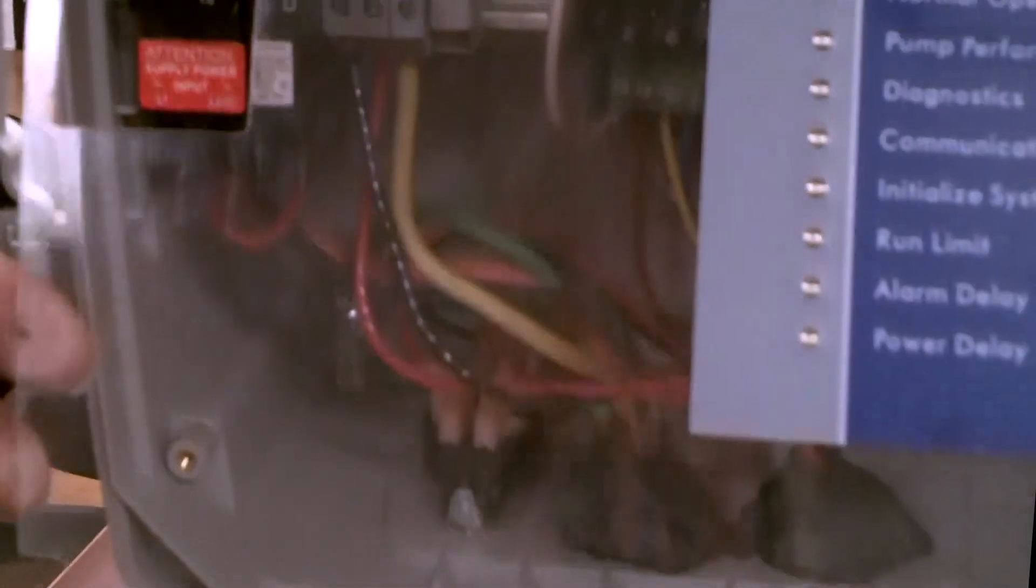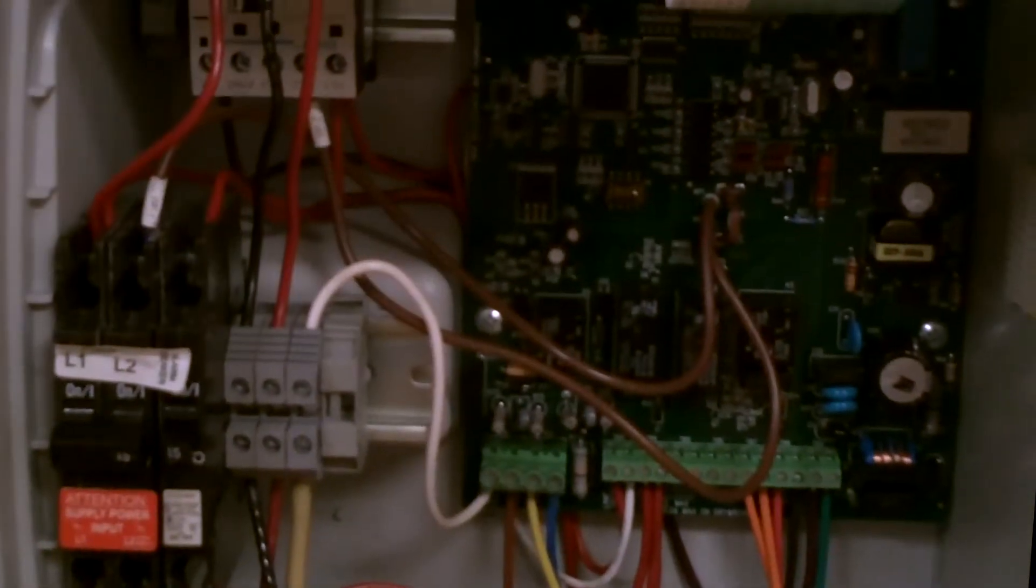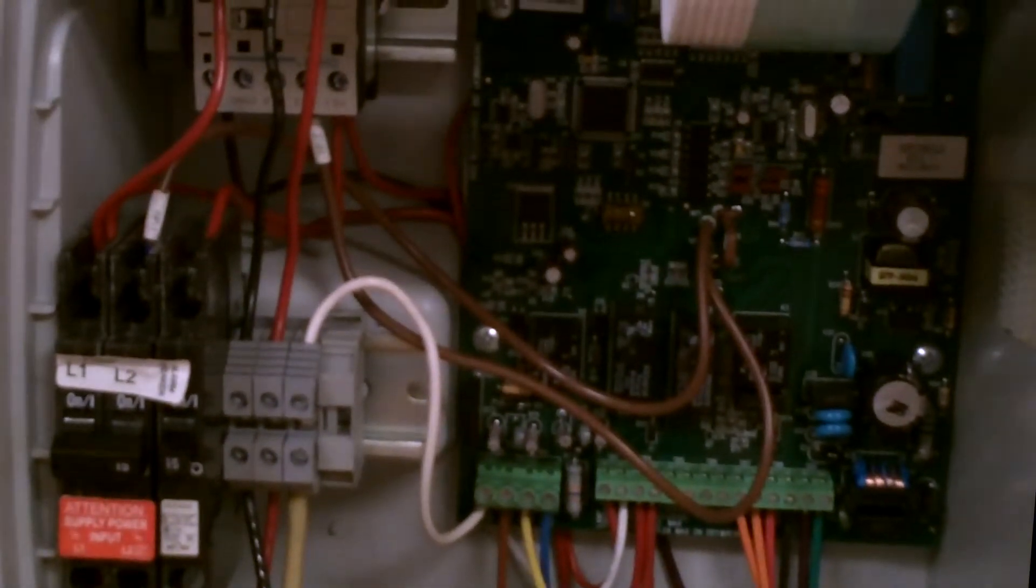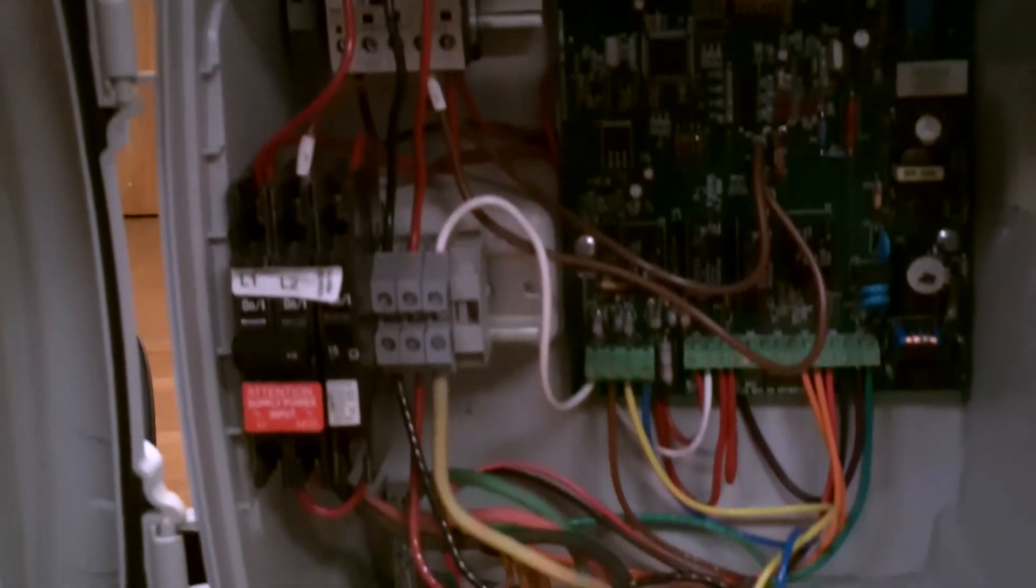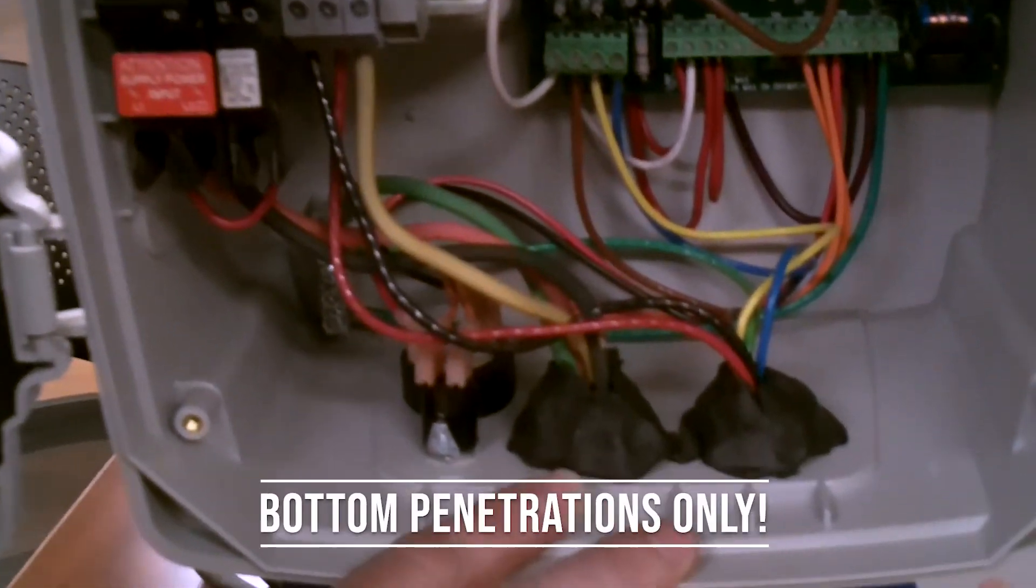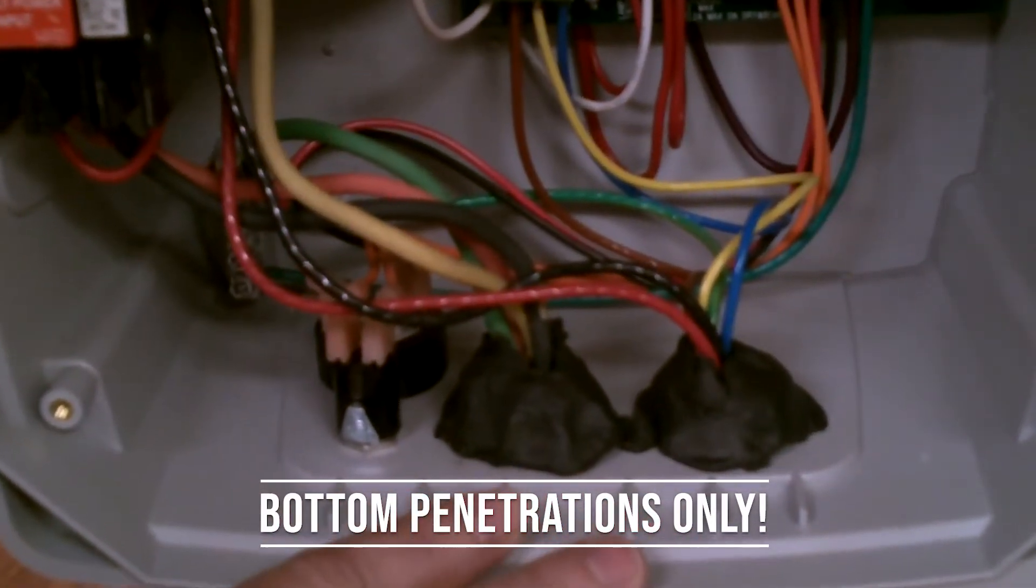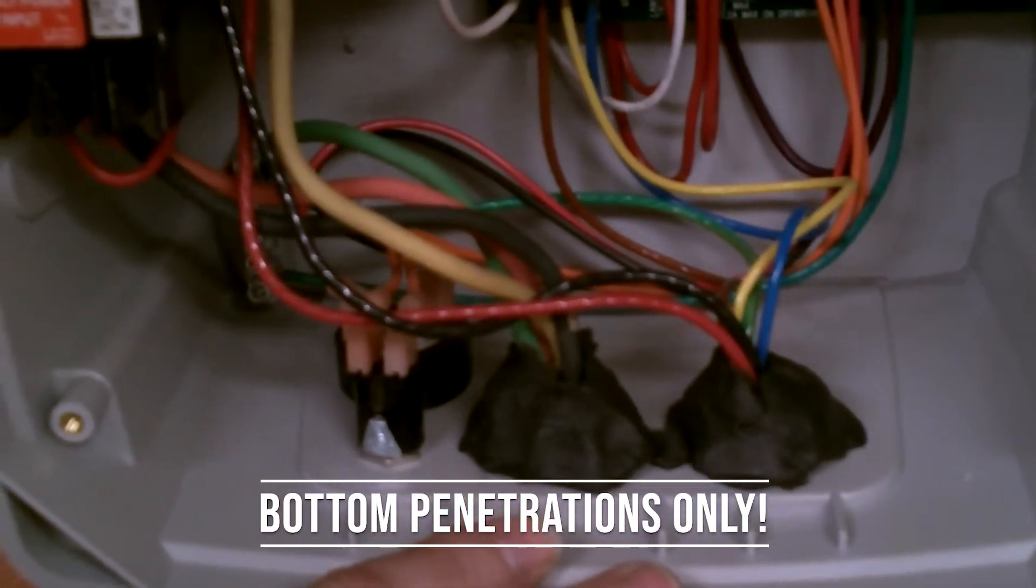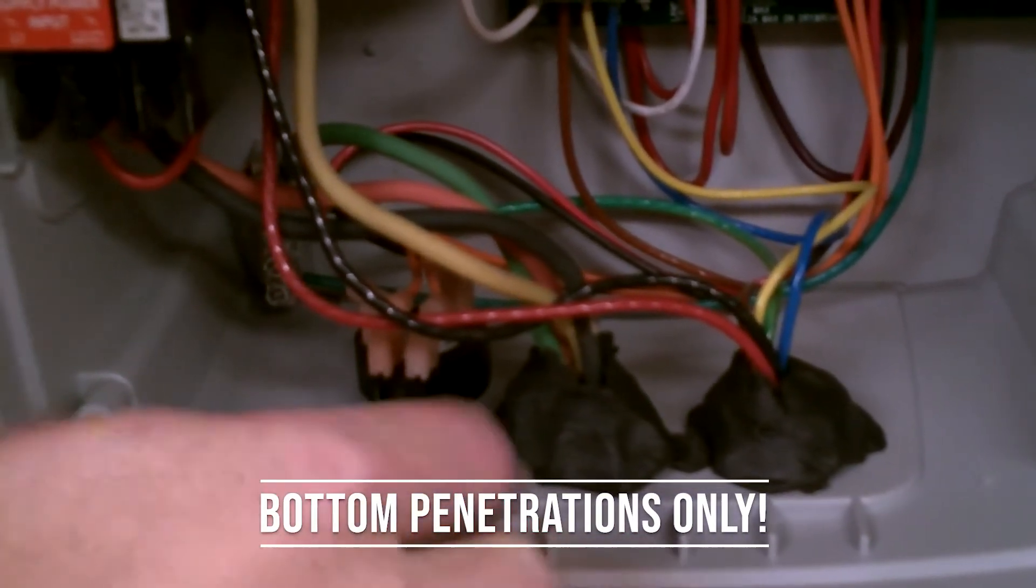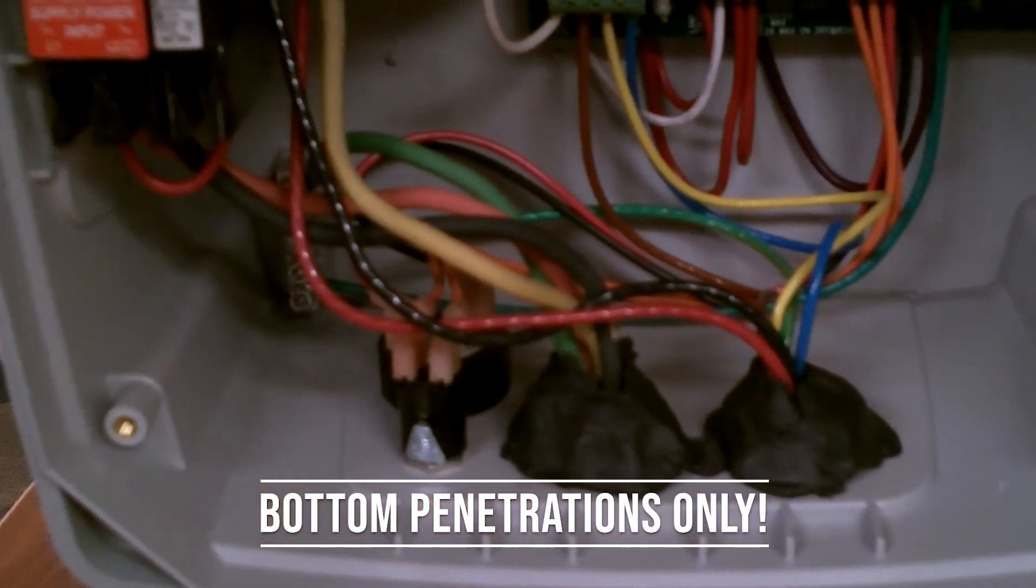Inside of the panel, just as a reminder, guys, make sure that you only penetrate the bottom of the box. If you penetrate the panel anywhere else, you're going to void warranty and you've also voided the NEMA 4X rating.